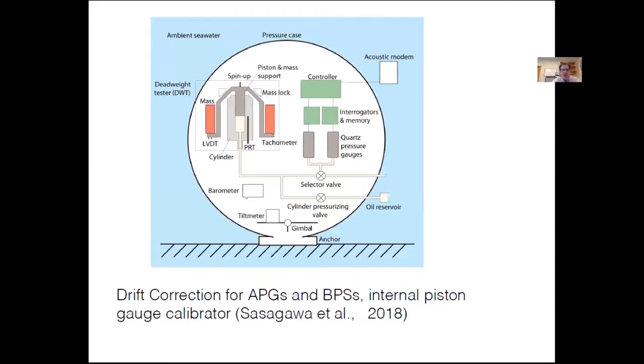The first system to accurately remove drift from pressure gauges was built by Glenn Sasagawa and Mark Zumberge. It uses a deadweight tester within the pressure case to produce an accurately known pressure signal. Your pressure gauges normally look outside the case measuring seawater pressure. Periodically, perhaps once a month, you spin up this system, switch valves so the gauges measure internal pressures, and use that to measure drift, then subtract it from your measurements.